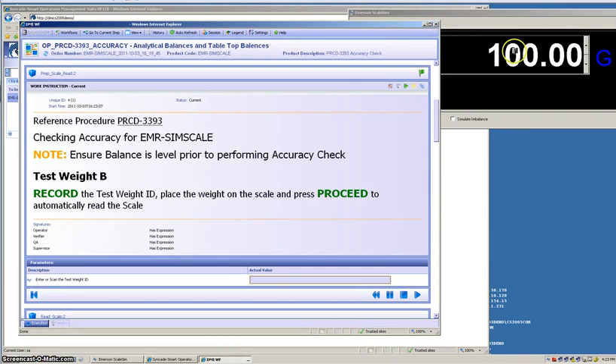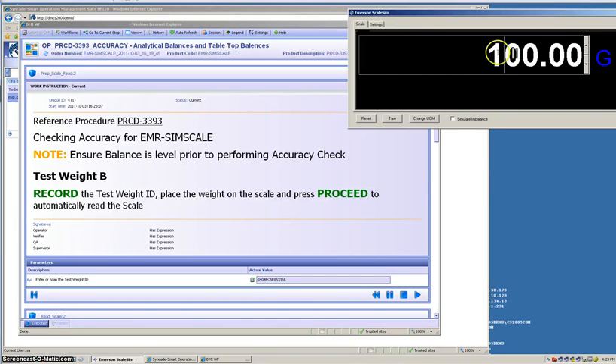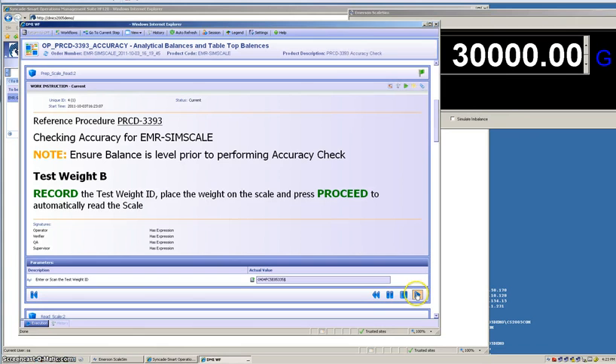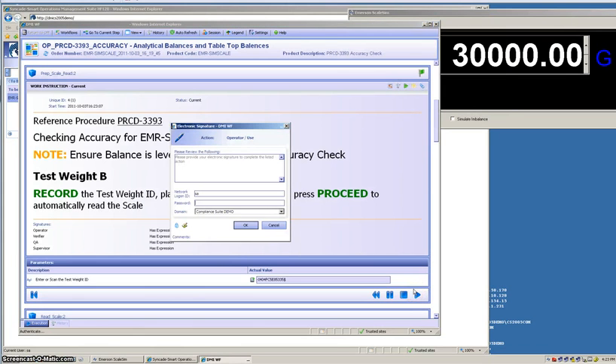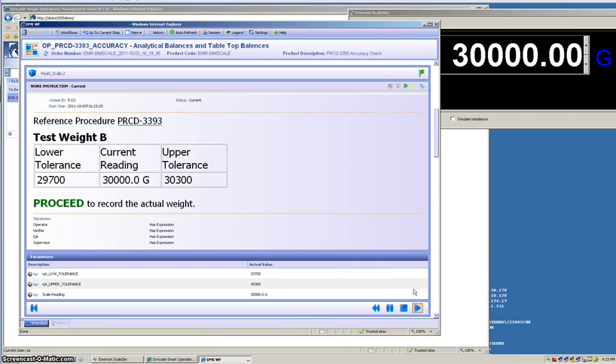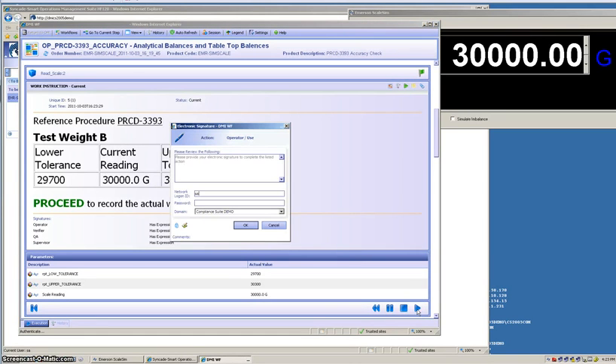Similarly, we're going to record the value of test weight B, and we are going to set it on the scale, and we'll set the scale to the correct value here prior to proceeding on, and then we're going to proceed. We're going to record our electronic signature. The system's going to go out and automatically read the scale and present us with the information. We're inside our tolerances. We're going to proceed to record the weight. And the system's going to complete the workflow.